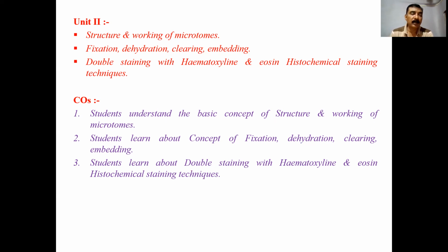Sectioning is not so easy. By trial and error, a number of problems arise during section cutting. Sometimes sections are compressed, sometimes there is splitting of the ribbon, sometimes the ribbon curves, sections get compressed or scattered, or alternate sections are thick and thin. These problems are there, and we have to overcome them. If problems are there, there are remedies. Last is the storage of the ribbon. We store the ribbon. Affixing process is there.